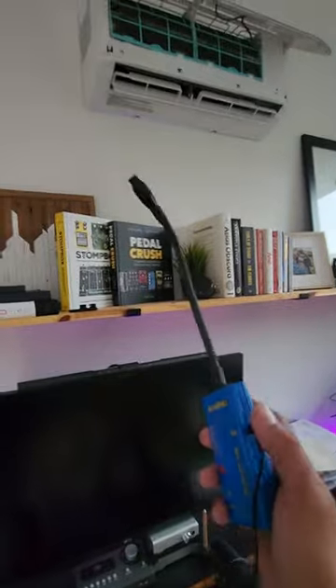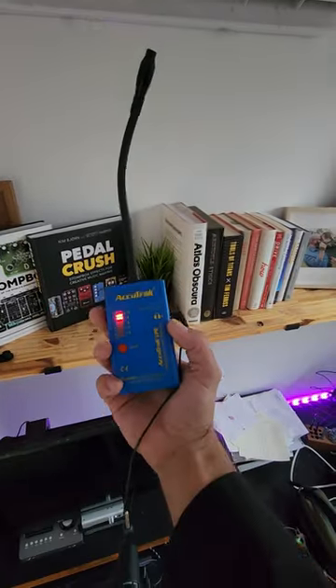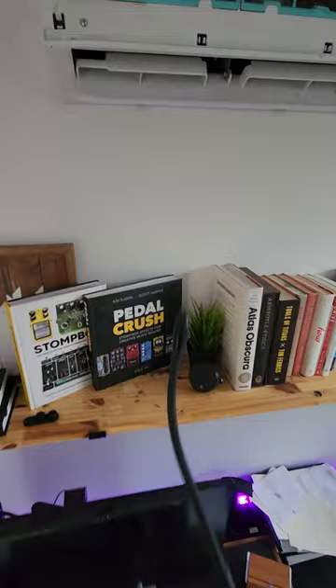We'll scan the air handler with the AccuTrak to check for leaks. Power this up — right off the bat we got a leak. In fact, I could hear it without this thing.